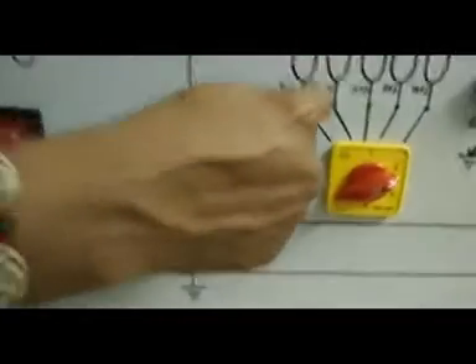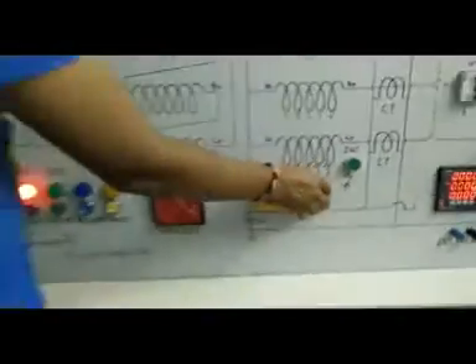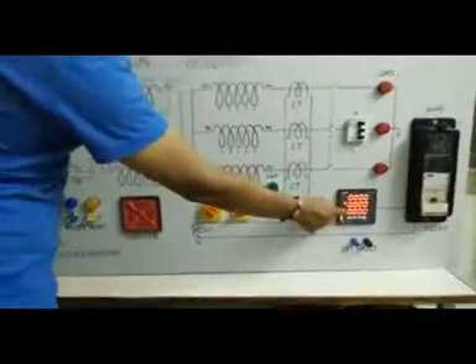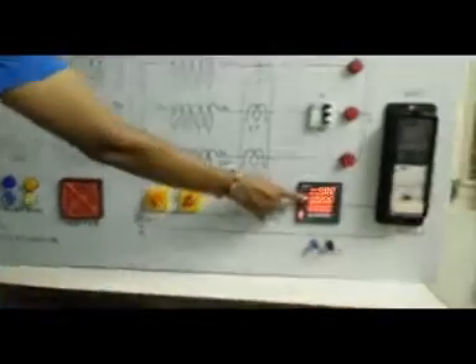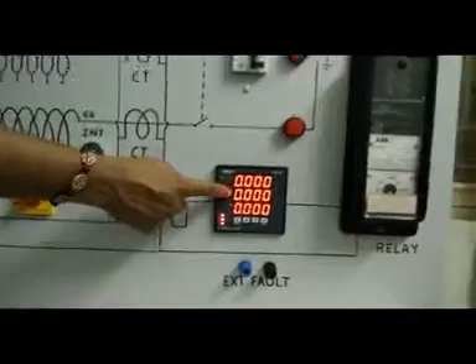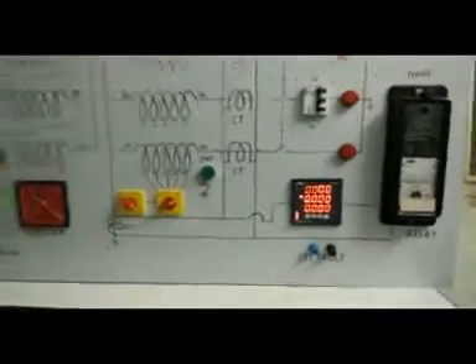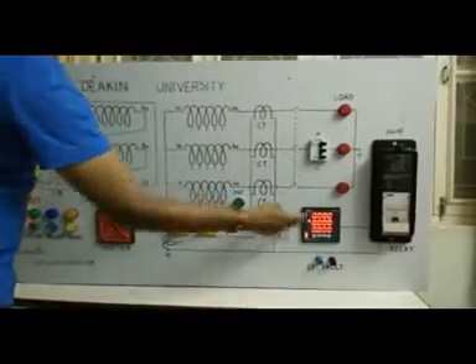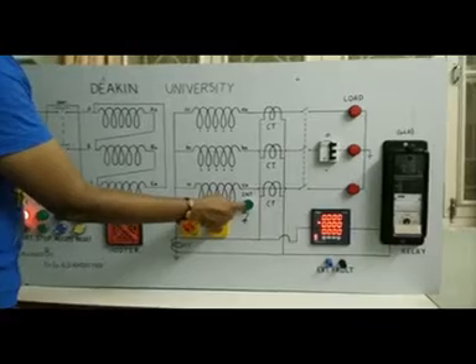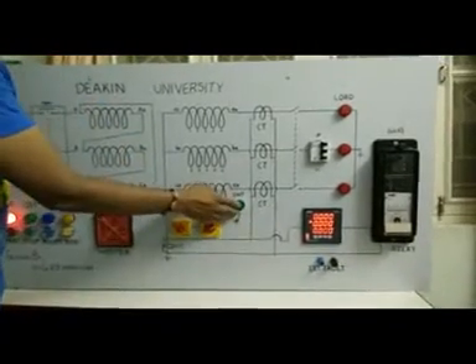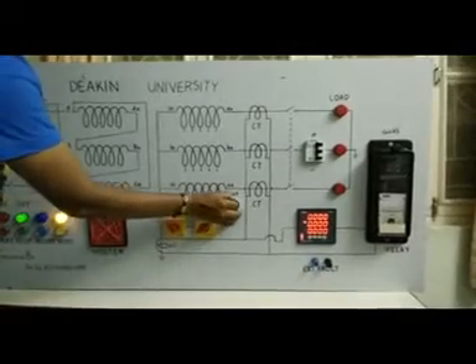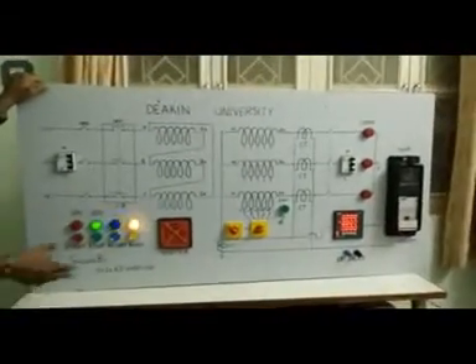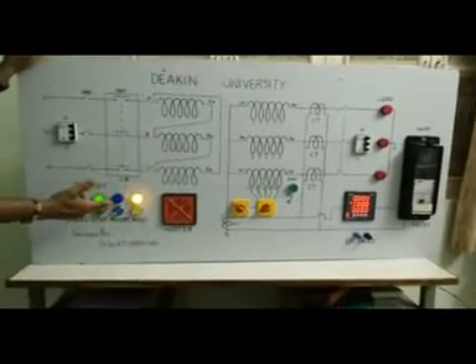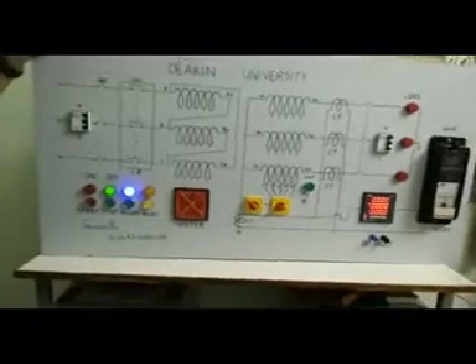Let's take the second tapping, which is 10%. So at the moment it is at 10% of the tapping, and now we will generate the fault. This is the digital ammeter with which we will be able to see the fault current. So please do have a look at the fault current, and even at the moment I switch the internal fault, please do have a look at the internal fault current. So this is how the fault has generated, and you can see the flicker and even the visual effect, so that we will be able to see the fault.